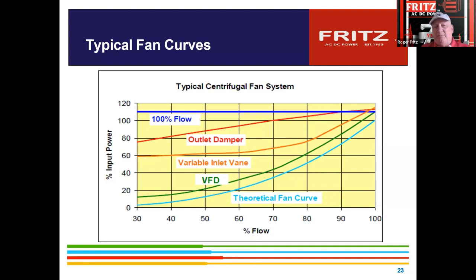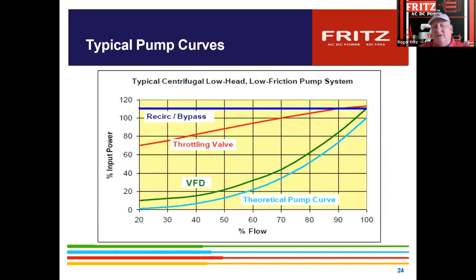And so there's a sweet spot on a pump where it was originally designed to run in a certain range and actually be at its optimal efficiency, up around 65–70% efficiency of the pump. If you go too far below or too far above, the curve goes off, and sometimes it'll drop down to 30%. And so you forfeit some of your savings. So it's definitely important to do an analysis well before we start, to see where we're at on the pump curves, and also on the vanes and those kinds of things. And it slows your ability to save.